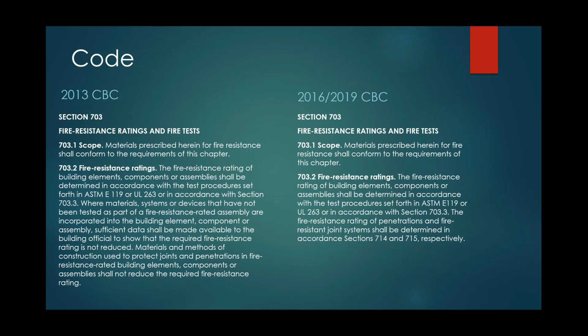So charging section, the scope of this is: materials prescribed herein for fire resistance shall conform to the requirements of this chapter. Fire resistance ratings of building elements, components, or assemblies shall be determined in accordance with the test procedures set forth in ASTM E119 or UL 263, or in accordance with 703.3. So that's where it leads you to 703.3. So the charging section is saying that building elements shall be tested in accordance with the standards of ASTM E119 or UL 263, or with the options given in 703.3. Then it continues on to say the fire resistance rating of penetrations and fire resistant joint systems shall be determined in accordance with 714 and 715 respectively. So if you've got penetrations, you go to 714 for the requirements, and for joints, you go to 715. Not here. 703.3 is for the building elements.